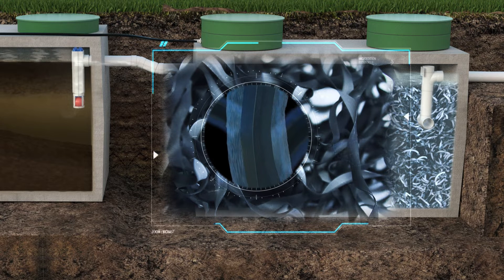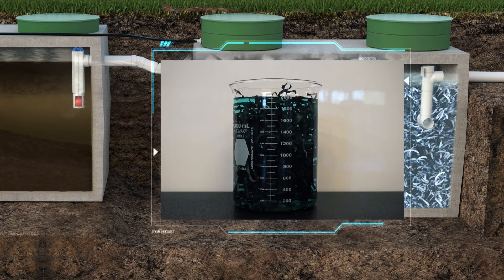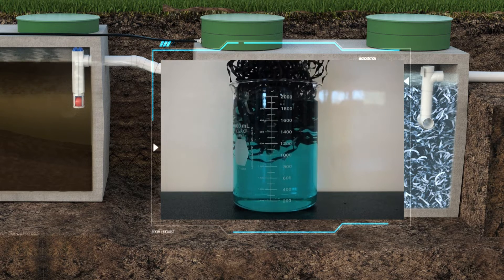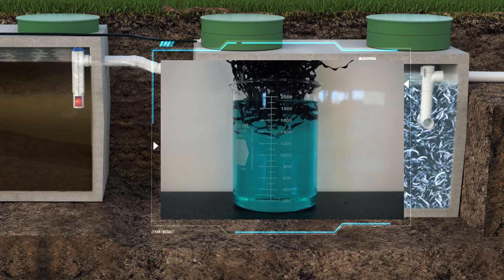The growth of the biofilm is resistant to both hydraulic and toxic shock. Only the exterior layers are affected and won't compromise continuous treatment. The media is self-supporting — it does not require energy to fill the whole volume of the tank. The media occupies only 3% of the tank volume and provides a compact yet robust treatment system.